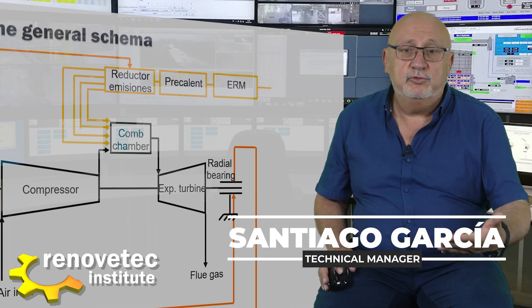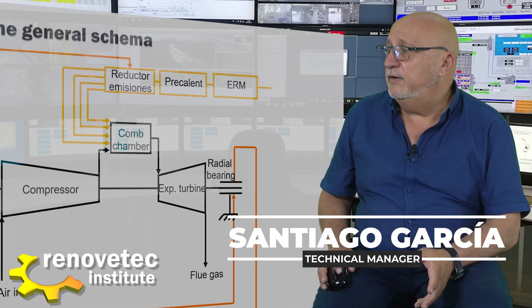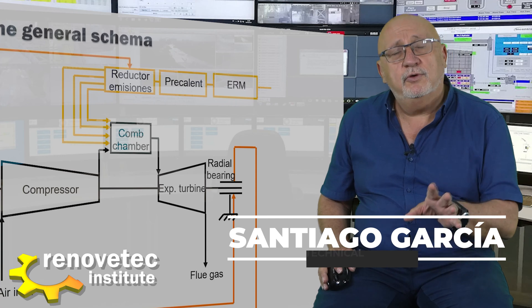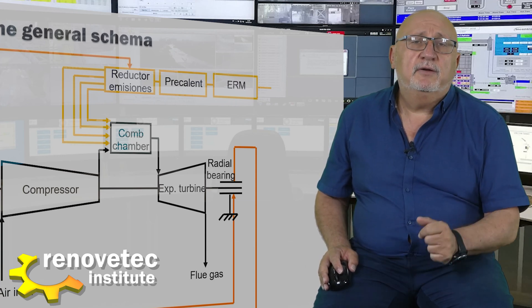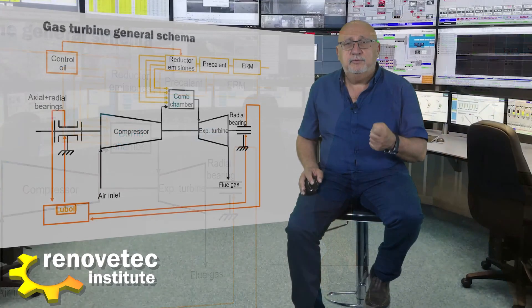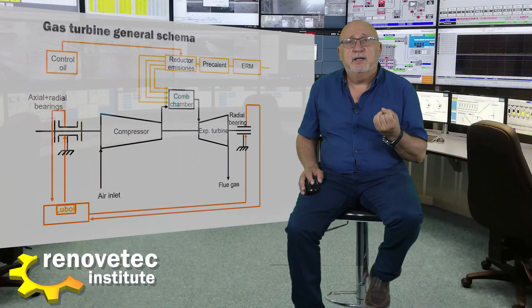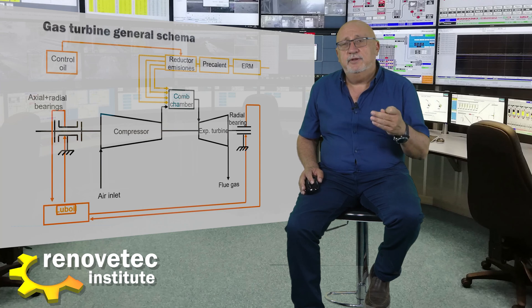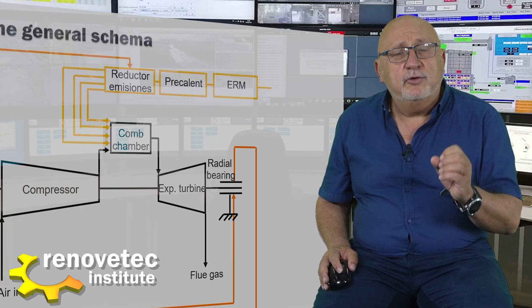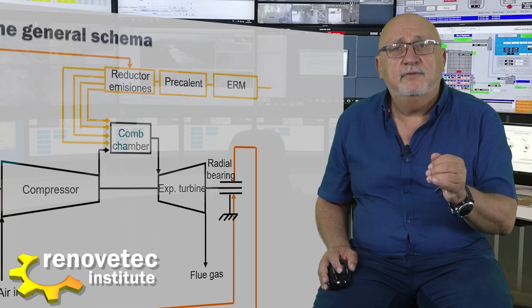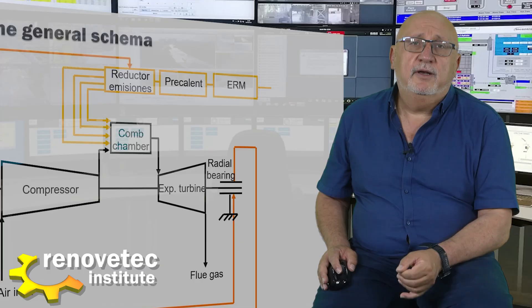To regulate the amount of gas entering the turbine, sometimes we have a control oil system to regulate this valve. We can regulate the valve with air, with an electric device, or with oil, but the most accurate system is to have a control oil system with a valve activated by oil.